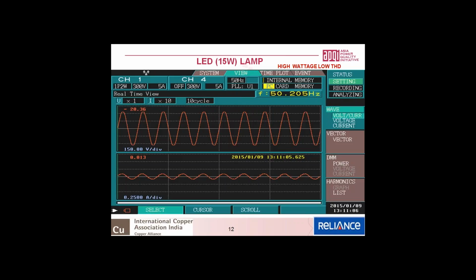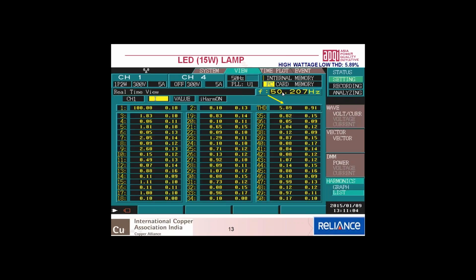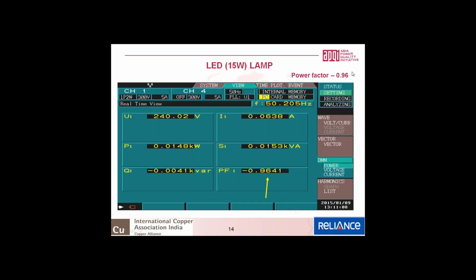This slide is a good LED, a 15-watt lamp of one manufacturer, whose waveform we have captured. You can see the bottom portion. The current waveform looks reasonably good. And if you see here, the total harmonic distortion is only around 5%. Therefore, it is an extremely good LED where the current distortions are very, very limited. And the power factor is excellent, 0.96, almost equal to unity. Therefore, this is a very good LED.